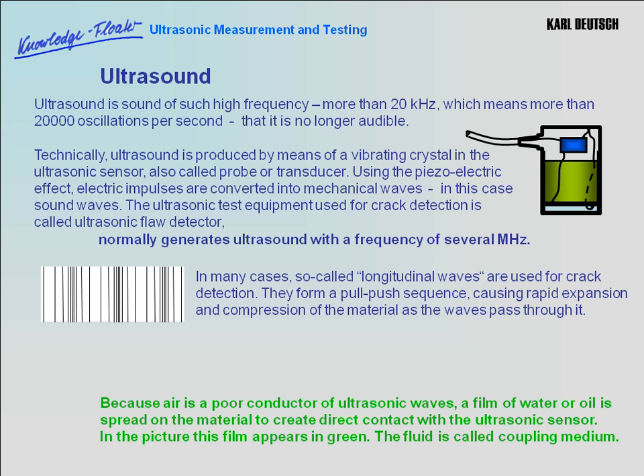Ultrasound is sound of such high frequency, more than 20 kHz, which means more than 20,000 oscillations per second, that it is no longer audible. Technically, ultrasound is produced by means of a vibrating crystal in an ultrasonic sensor, also called probe or transducer. Using the piezoelectric effect, electric pulses are converted into mechanical waves, in this case sound waves.